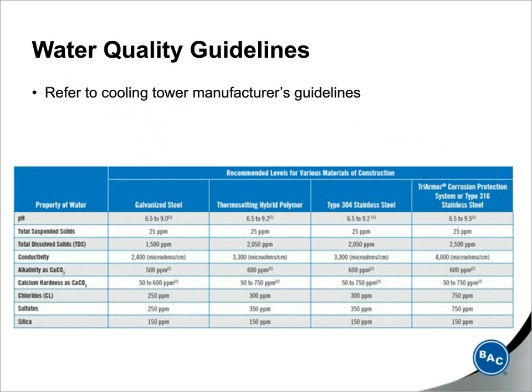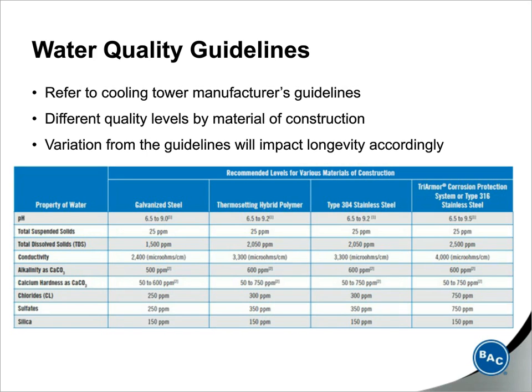Always make sure that you consider the cooling tower manufacturer's water quality guidelines. This table that's shown here includes BAC's guidelines, which are pretty typical for the industry. Now, note that there are different guidelines for each material of construction, and remember, these are general guidelines based on empirical data and historical data. So deviating from the manufacturer's guidelines, all it's going to do is affect the cooling tower's lifespan accordingly. And as I said earlier, depending on the water quality of your system and the allowable levels of corrosion that you're willing to accept, you can choose materials that allow you to save water and reduce your total cost of ownership.